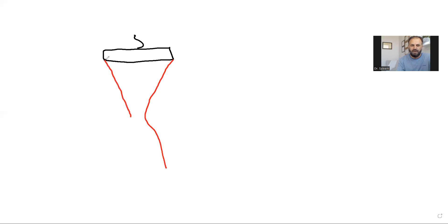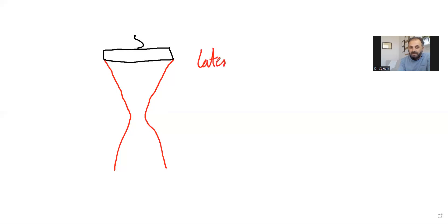If I want to have better overall image quality — the entire picture at its best — I have to do two things. Number one, I want the axial resolution to be the best, so I have to select a higher frequency probe. Now, how about lateral resolution? Let me draw a probe. We know this transducer gives us a sound beam. The sound beam converges to a point and then diverges after that. Where the beam diameter is the narrowest, the image quality for lateral resolution will be best at that point. So lateral resolution is determined by the beam diameter.